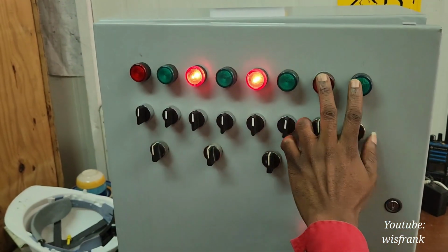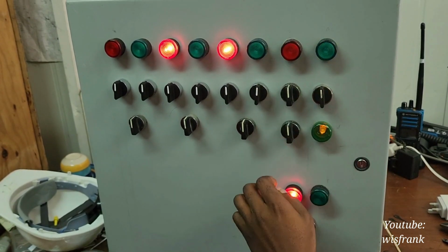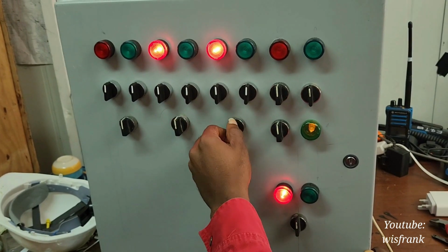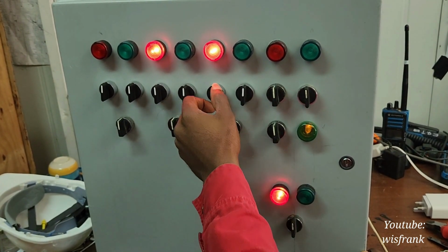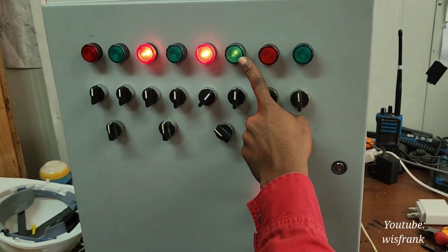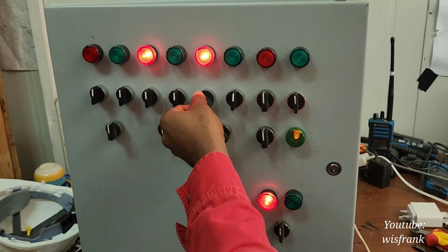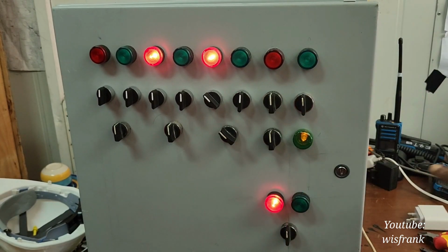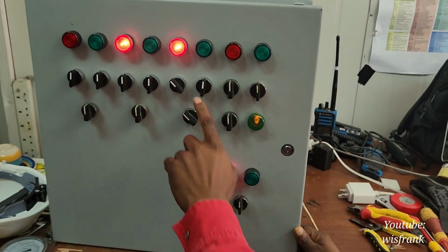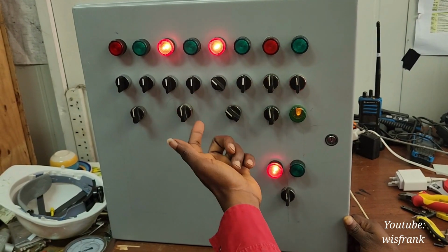So here we have our indicator for pump A and pump B, and here we have the master control for each of these pumps. If you turn it to pump A, let's take for instance, let's come to this one so you can see clearly. You turn it to pump A, you can select pump A on hand, and it tells you that the pump is running. That's manual. On manual it is running. Then if you turn it this way, it switches to auto. But right now, because we have a terminal in here that needs a pressure switch to activate it on auto, that's why you're not seeing it running right now. But when it gets to the field, you will see that this one will run.